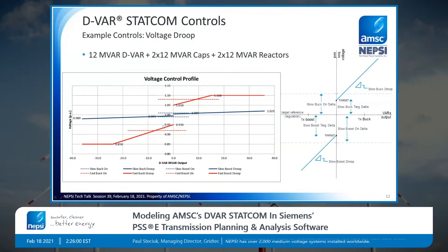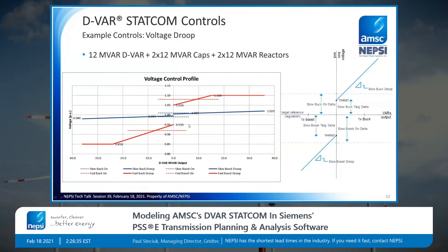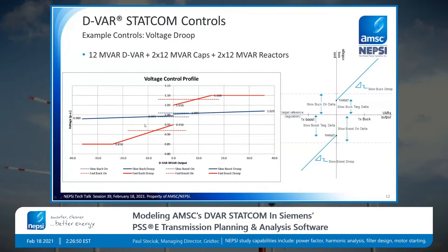If the voltage deviates to extreme events — outside approximately 92% to 108% voltage — the red curves take over. This is where the STATCOM utilizes its overload. If voltage is below 85%, the STATCOM goes to full 3x current output. This concept of dual droop controls — transient and regulation together — is a unique control feature that allows quite a bit of customization and application-specific parameters.